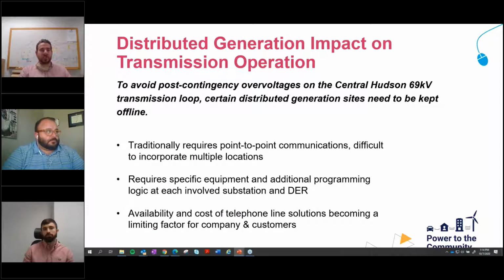Next slide. So the problem that occurs with this line is this bulk amount of generation in one spot — if the line has any switching, an outage, and the line configuration changes, we can end up with over voltages on the transmission system. It's not something that's going to occur regularly, but it is a risk. So in order to mitigate that risk, we would have to do something to take these sites out when the line is in an abnormal configuration, or not allow them to come online. Not allowing them to come online isn't really a feasible option, so then it's how do we accommodate them and deal with the risk of abnormal conditions.